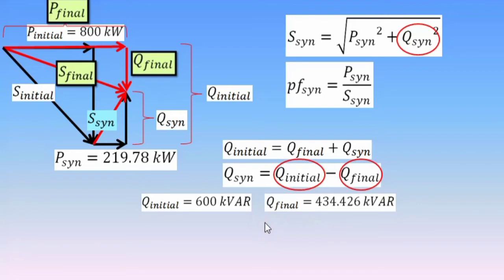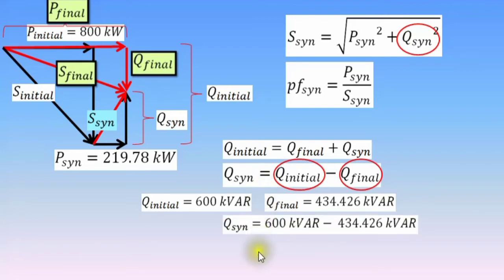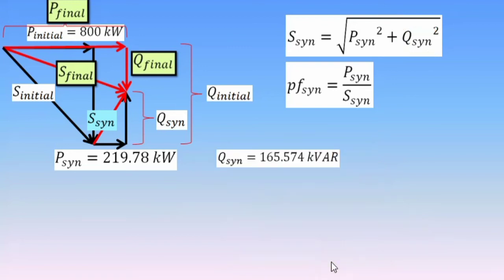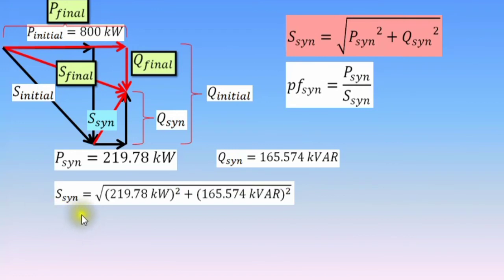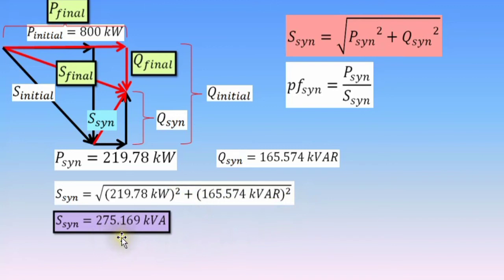value of the reactive power of the synchronous motor. Substitute the values, 600 kVAR minus 434.426 kVAR, the answer is 165.574 kVAR. And now that we have the values of the effective and reactive powers of the synchronous motor, let's substitute them to this equation. Apparent power of the synchronous motor equals the square root of 219.78 kilowatts squared plus 165.574 kVAR squared. The answer is 275.169 kVA. This is the value of the kVA input of the synchronous motor.